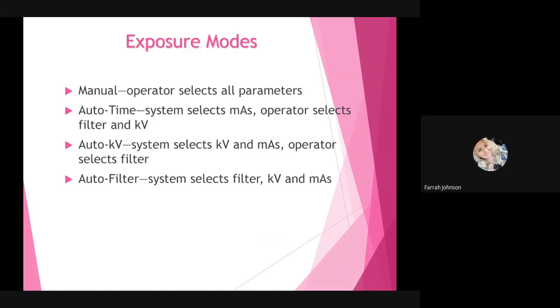So, exposure modes. We have manual, where the operator selects all parameters. You have your auto time, which is when the system is going to select your mAs and the operator selects filter and kVp. Then you have auto kV systems, which are going to select the kV and the mAs, and the operator selects the filter. And then lastly, you have an auto filter system, which is when the system selects the filter, the kVp, and the mAs.